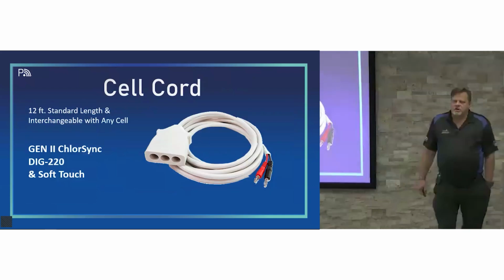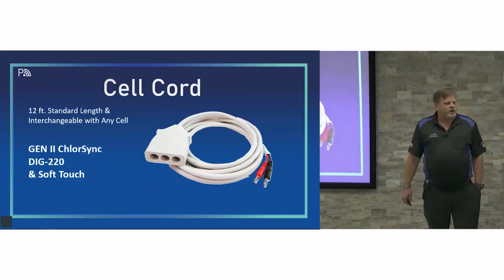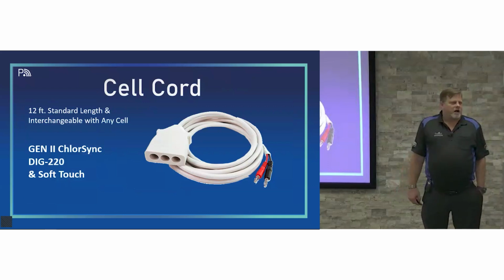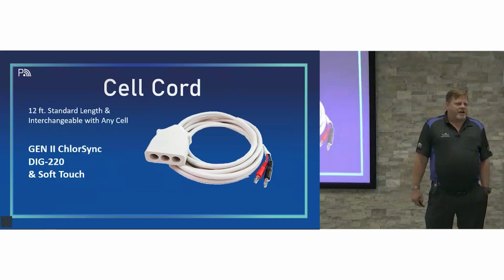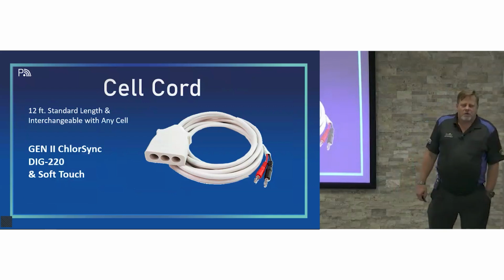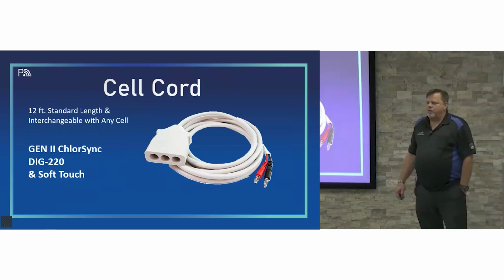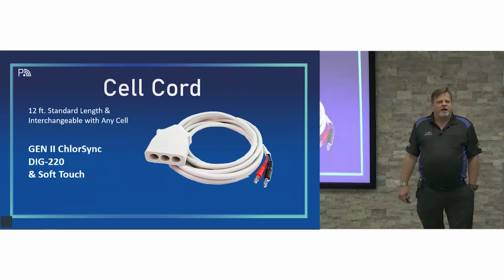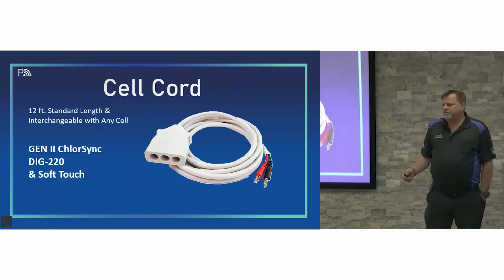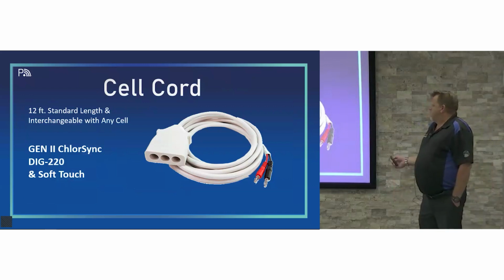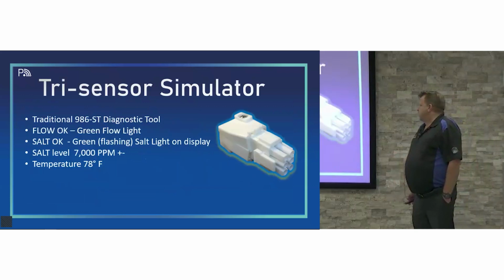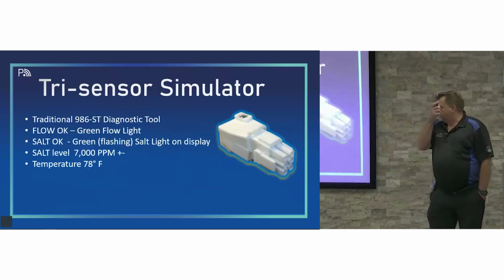The cell cord takes the same cell cord as the Soft Touch or Dig 220, if you're familiar with that, which is basically the red and black RCA jack / banana plug connections. We found we had fewer failures with that, which is why we went with it versus the mate-and-lock white connectors. Standard length is 12 feet, same thing with the tri-sensor cord, which is also 12 feet.